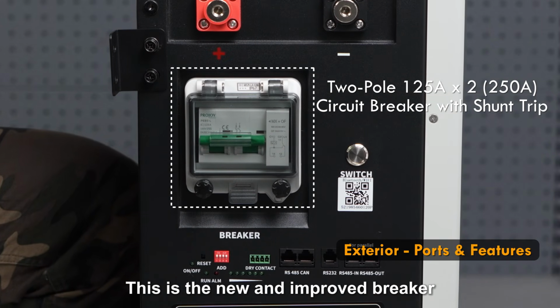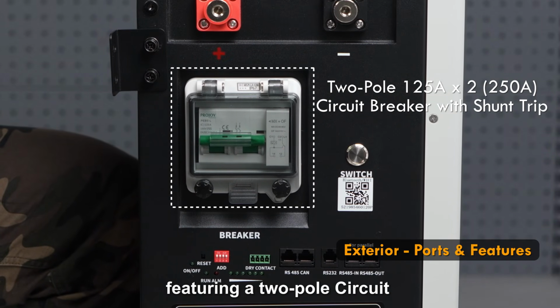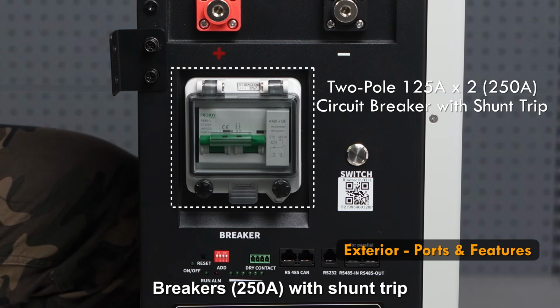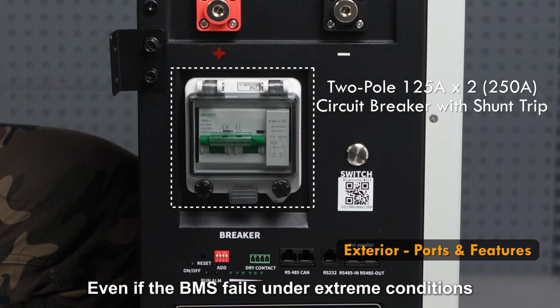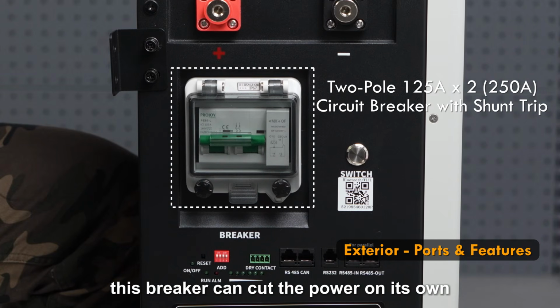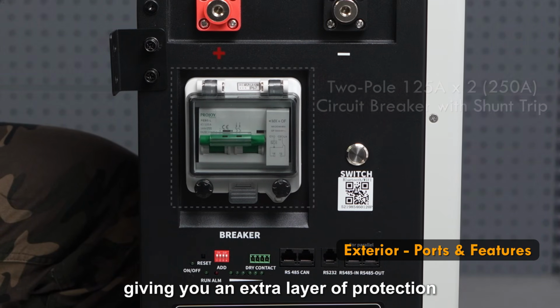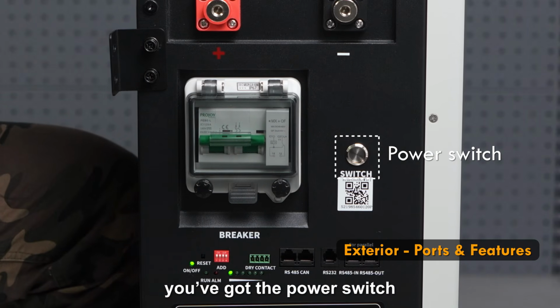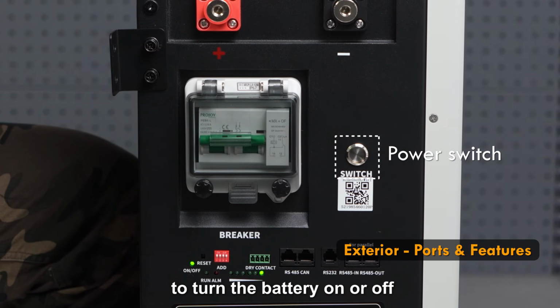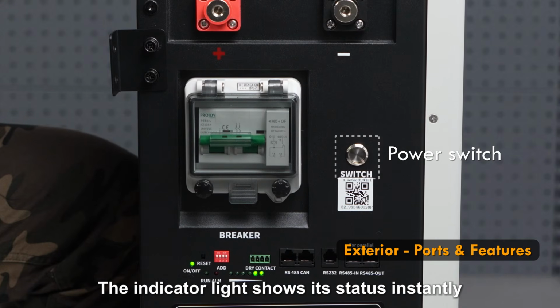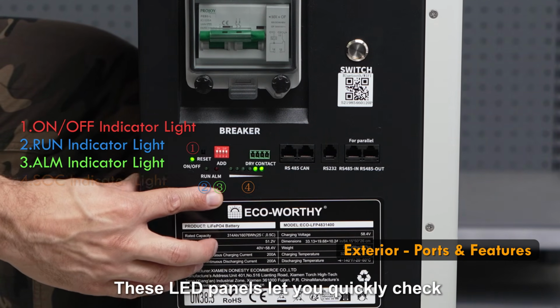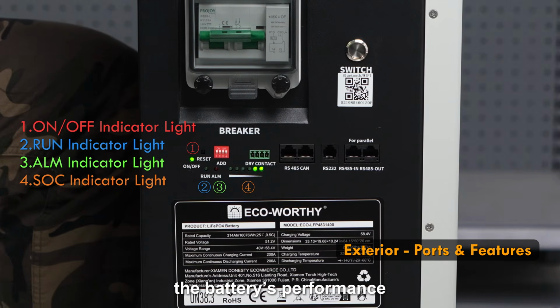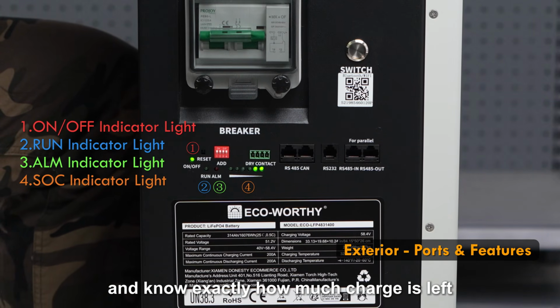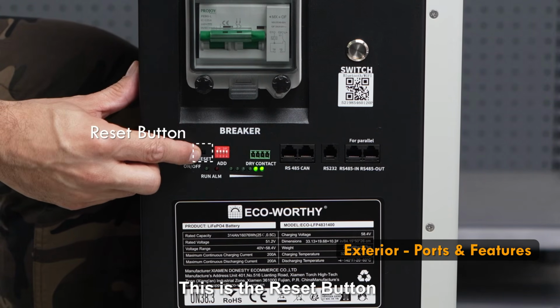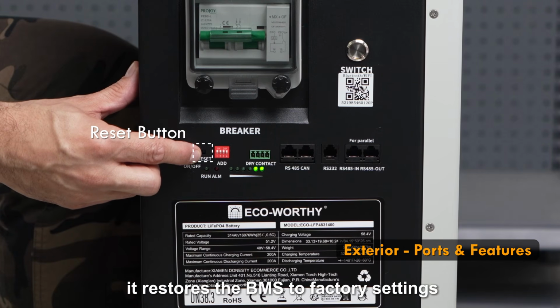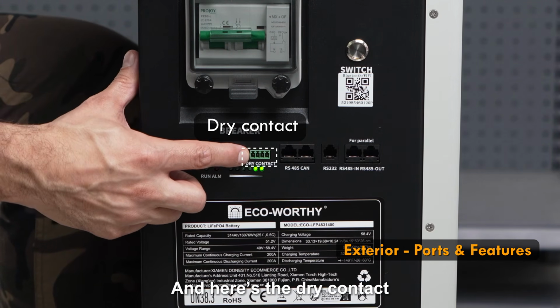This is the new and improved breaker, featuring a 250 ampere thermal magnetic trip switch with a separate release. Even if the BMS fails under extreme conditions, this breaker can cut the power on its own, giving you an extra layer of protection. Right here, you've got the power switch to turn the battery on or off. The indicator light shows its status instantly. These LED panels let you quickly check the battery's performance, see any issues and know exactly how much charge is left. This is the reset button. It restores the BMS to factory settings. And here's the dry contact.